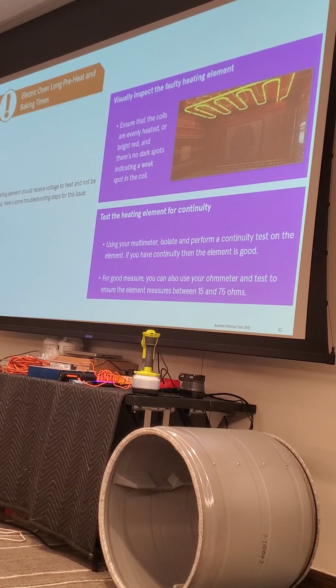They should turn bright red when they're heating and should go off and on according to what your temperature needs to be. Like I said, you can ohm those out, you can isolate them, you can test them. Okay? This one says 15 to 75 ohms.